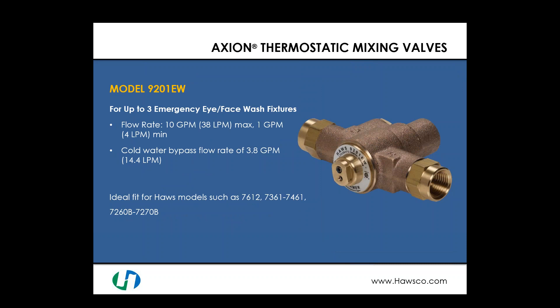Looking at the Haws mixing valve line, there are several valves to choose from. Starting at the lower end of flow rates, we have the model 9201EW. This valve is designed for up to three emergency eye face wash fixtures with a maximum flow rate of 10 gallons per minute and a minimum of 1 gallon per minute. In the event of a hot water failure, the cold water bypass is 3.8 gallons per minute. The 9201EW is an ideal fit for Haws models 7612, 7361, 7461, 7260B, and 7270B.